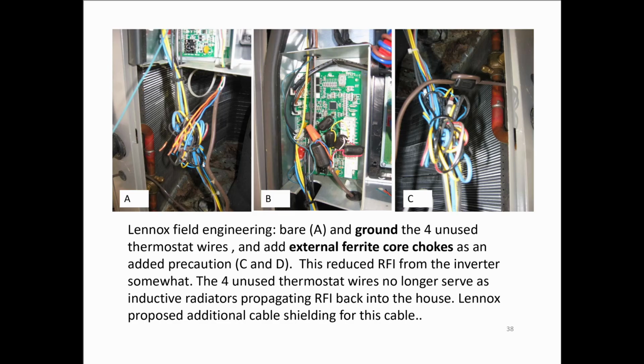Now I'm going to talk quickly about my second problem. I was getting tremendous RFI from my furnace. Well, the field engineer came out and the dealer sent out a technician, and he said there's no question at all that the RFI is from the inverter. The reason they could tell was they turned on different things independently, including the condenser fan and the compressor. And when they turned on the compressor, I got tremendous RFI. And when they turned it off, it went away.